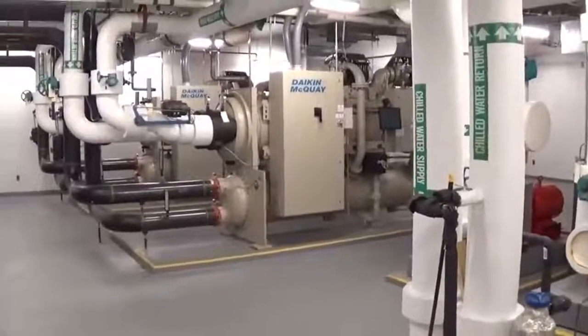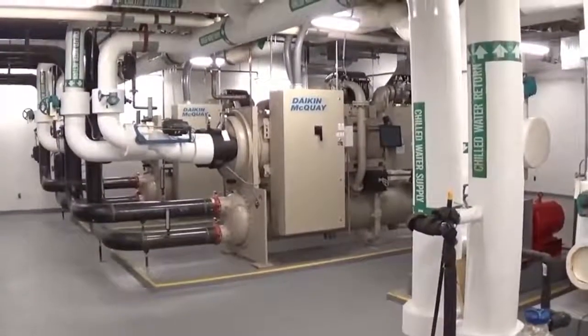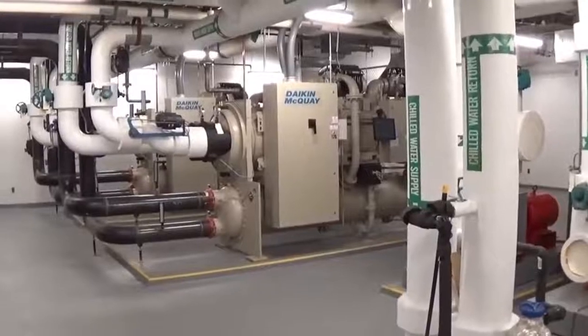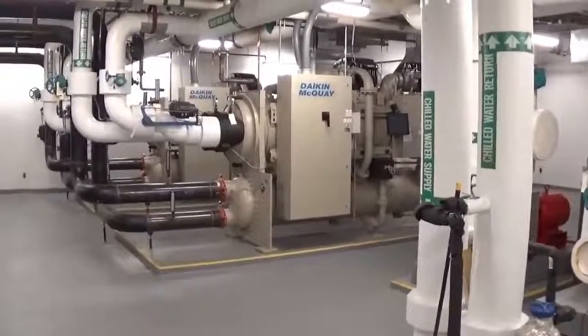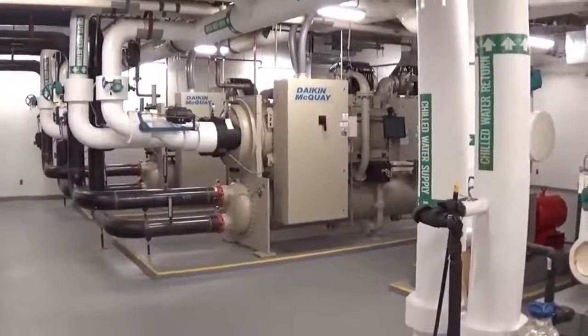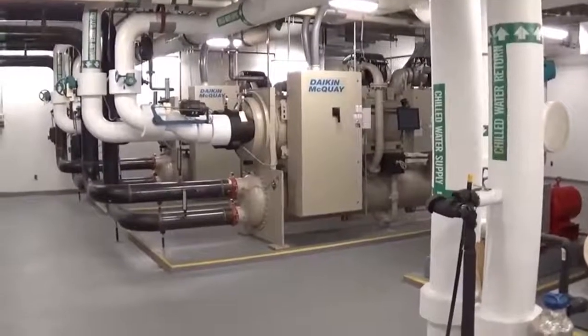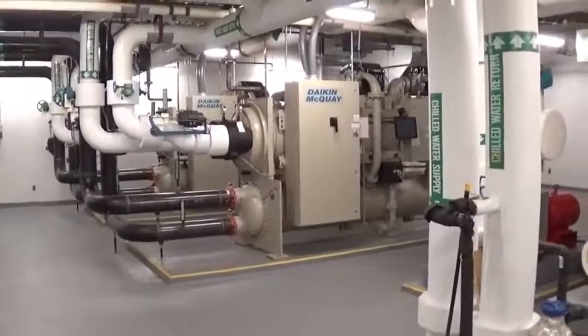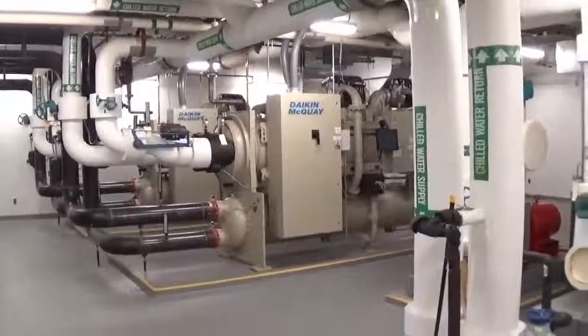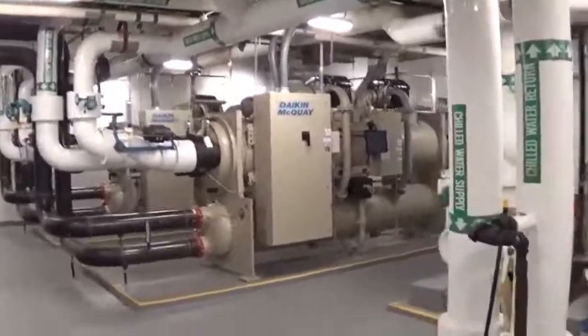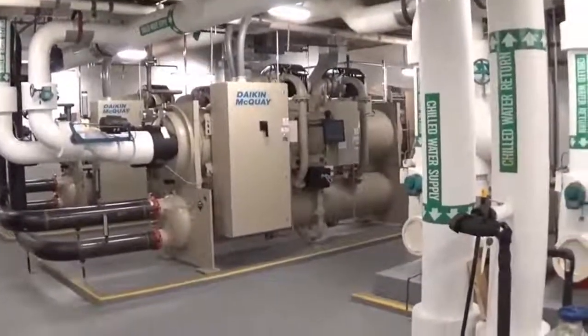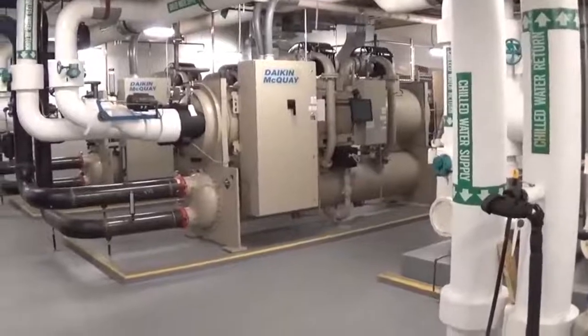So we have two 400-ton chillers that I'm looking at right now. These were updated. The original chillers used old-fashioned refrigerant, R11 refrigerant, and they were removed in a renovation and replaced with these high-tech Daikin McQuay chillers.